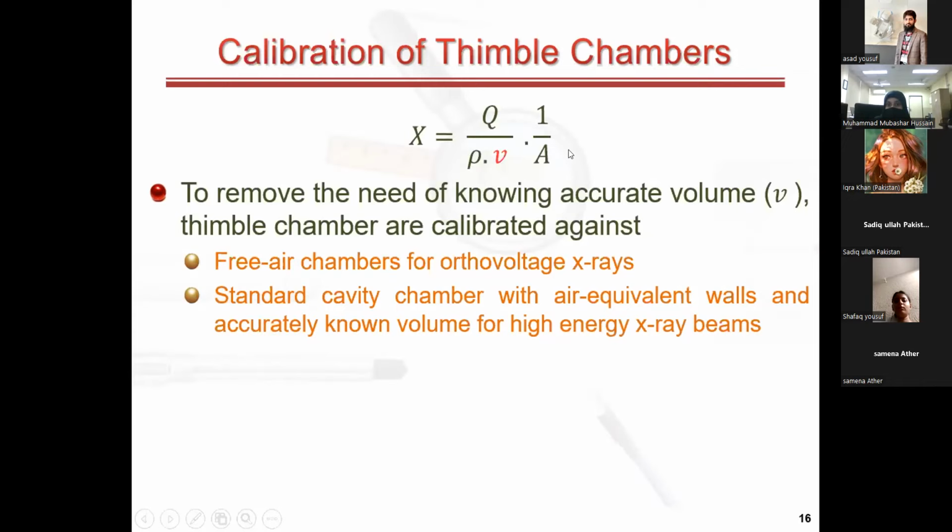However, for high energy X-rays, these thimble chambers can be calibrated against a standard cavity chamber, like a Farmer chamber, with air equivalent walls. And again, for these standard cavity chambers, their volume is accurately known. And then we don't need to have knowledge of the accurate volume of our thimble chamber.